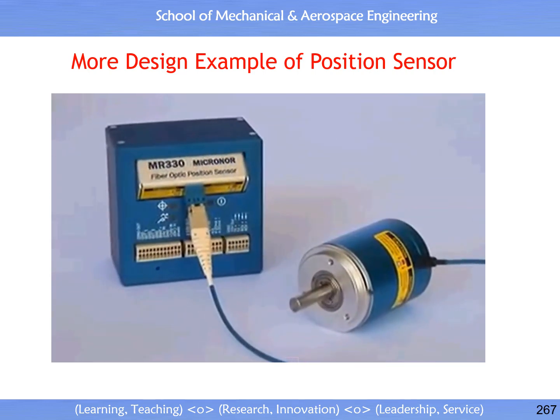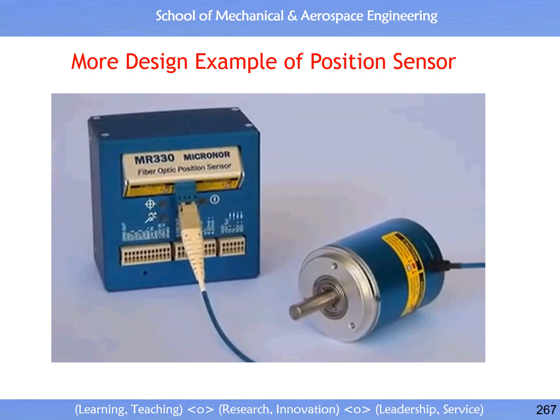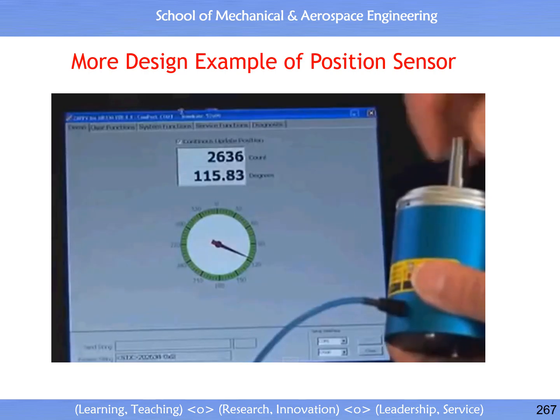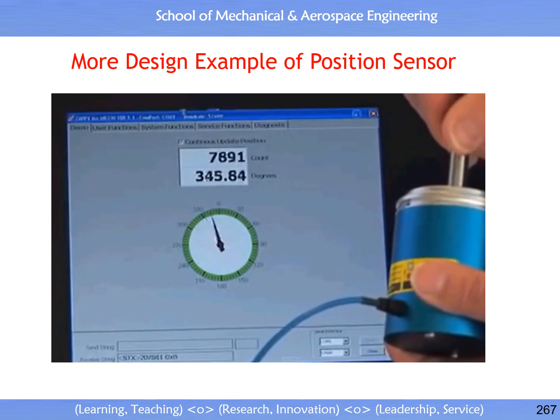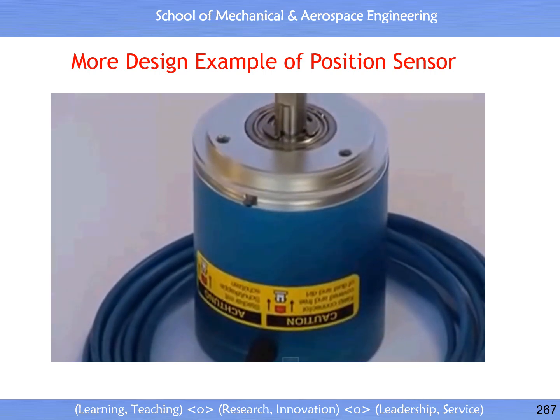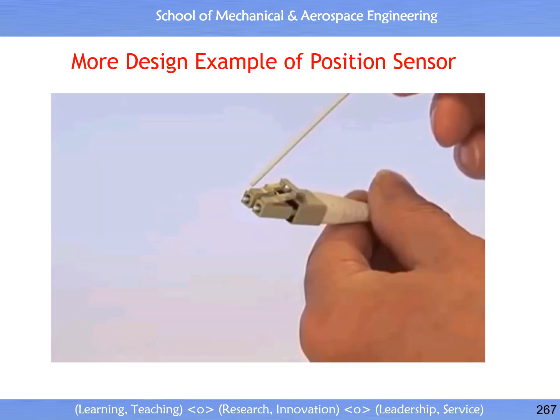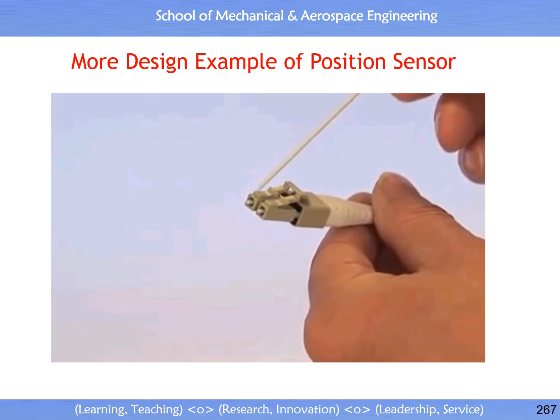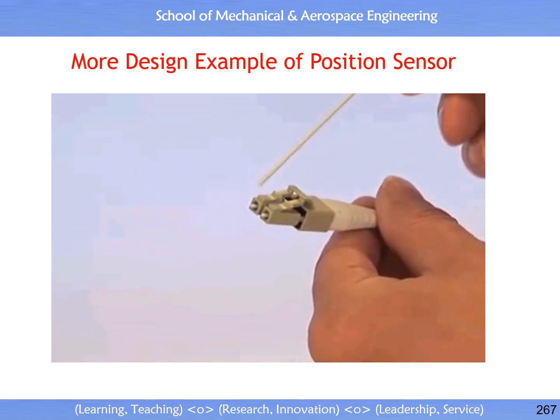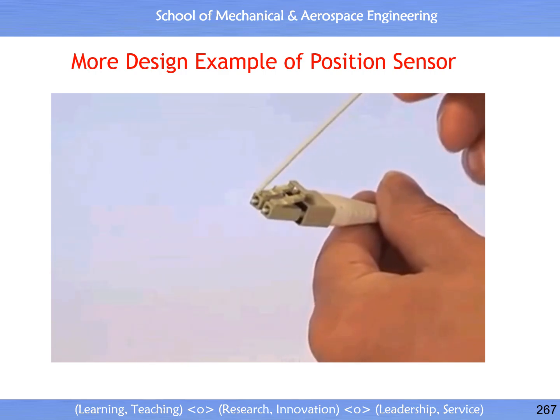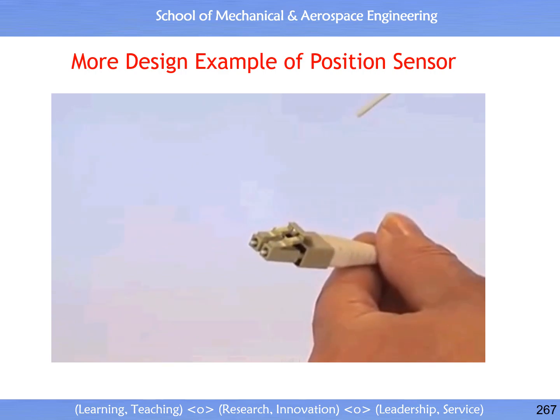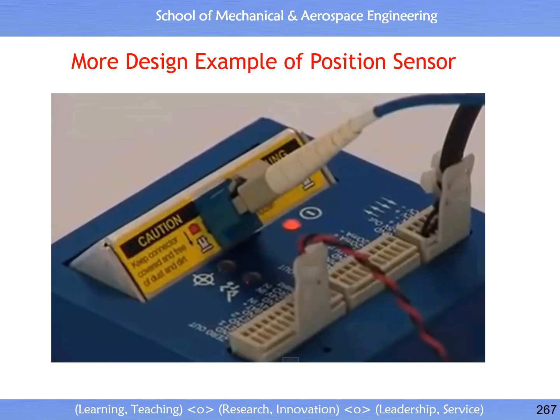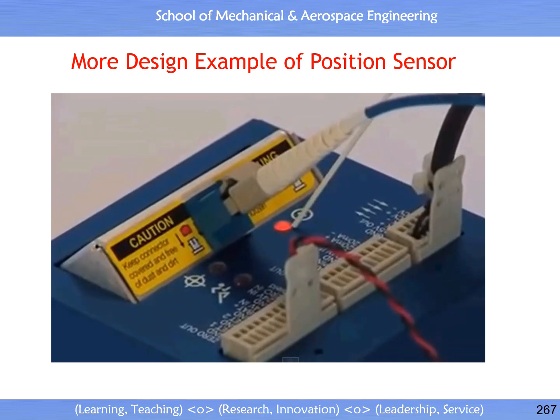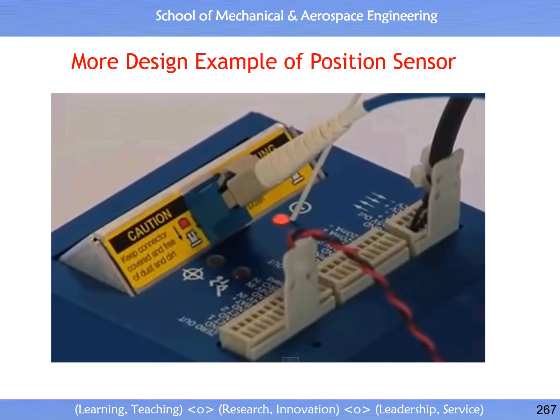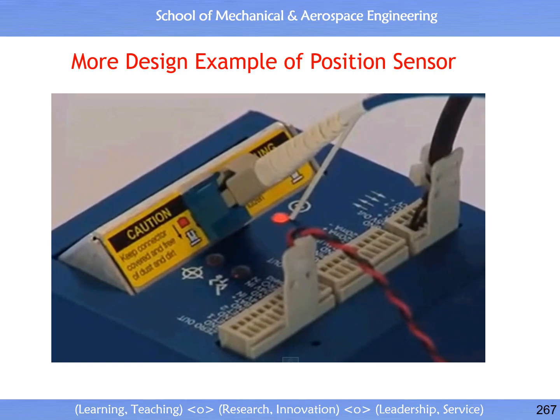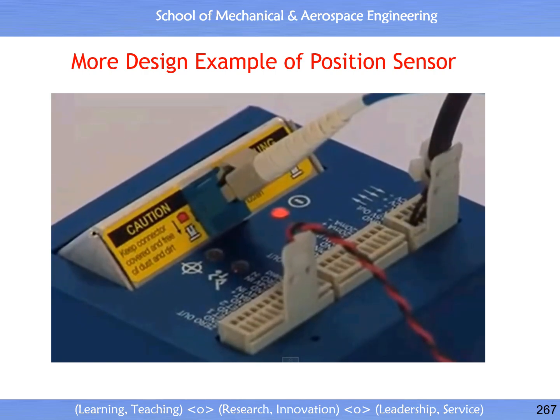Micronor's novel fiber optic position sensor consists of a sensor and a controller. The system is connected by a duplex fiber optic cable. No electrical connection to the sensor is required. There's one fiber optic strand for transmitting light to the sensor and one fiber optic strand to receive the light with the position information from the sensor. A push-pull fiber connector makes connection to the controller simple. An LED status indicator confirms that the connection to the sensor is completed and that the system is functioning properly.